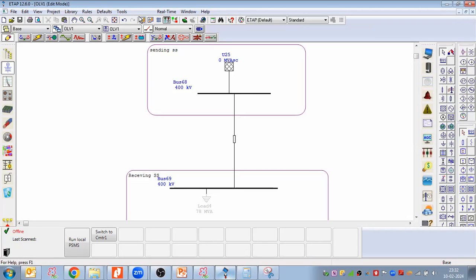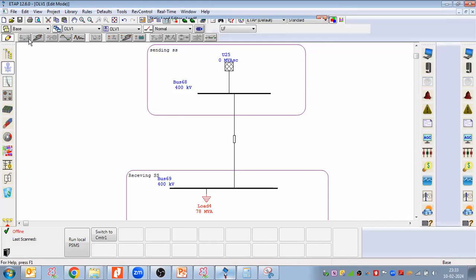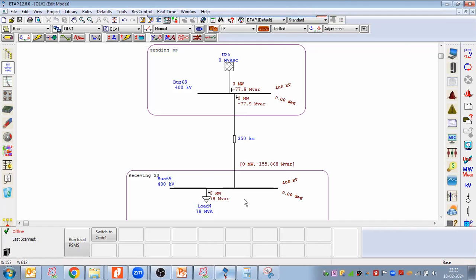Sir, what will happen if we connect a 100 megawatt load on this bus? In this case, how does the shunt reactor respond? Consider 100 MVAR load, 100 megawatt load at the receiving end. So my sending substation sends 100 megawatt to the receiving substation - what will be the condition then, and what will happen with our reactor? Will it be opened or kept energized with the bus?